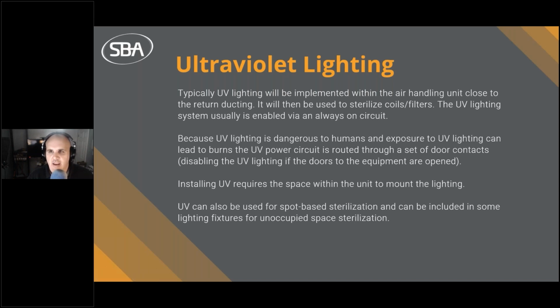It's implemented in the air handling unit close to the return ducting, and then it's utilized to sterilize coils and filters. Now, the UV lighting, it's usually enabled via an always on circuit, meaning if the system's on or if it's off, meaning the air handling system, the UV lighting's still going to be on. Now, because UV lighting is dangerous to humans and exposure can lead to burns, the UV power circuit is typically routed through a set of door contacts, which disables the UV lighting if the doors to the equipment are open. So that's typically how it works.